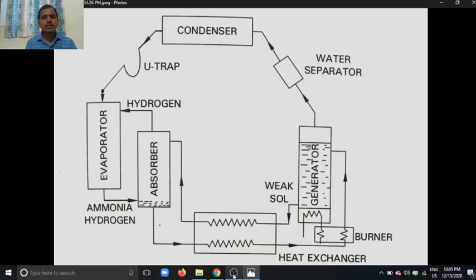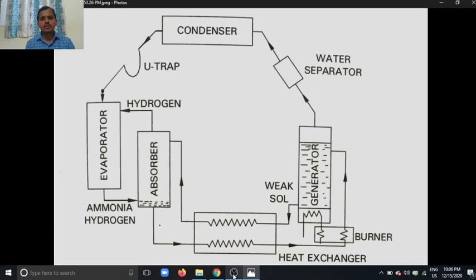Good morning. Today our topic is the Electrolux refrigeration system, which is also called a three-fluid refrigeration system. In this system we are using three fluids: ammonia, water, and hydrogen. Ammonia is used as a refrigerant, water is used as an absorbent, and the main function of hydrogen is creating low pressure in the evaporator and promoting the evaporation of ammonia.